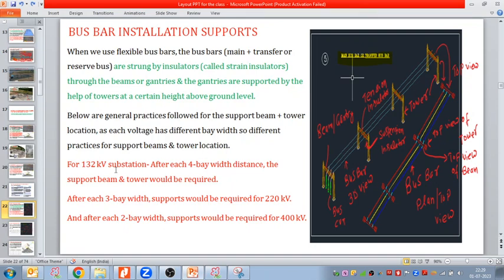If we have any 132 kV substation, then after each 4 bay width distance, the support beam and tower would be required. It means here one support gantry and tower, then 1 2 3 4 bays I will take, and after that I will plan the next beam, next support, and then again 4 bays and the next support. If there are only 4 bays, in that case we can plan all the bays with the help of only two gantries, or sometimes if we want to go on the safer side, we can split between two here, and after that again we can take two, but four is also acceptable. But that again will depend on the voltage, right?